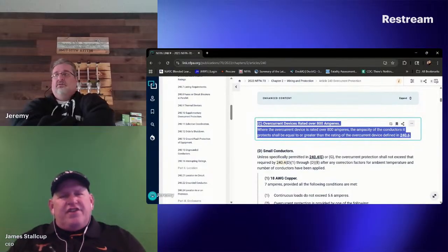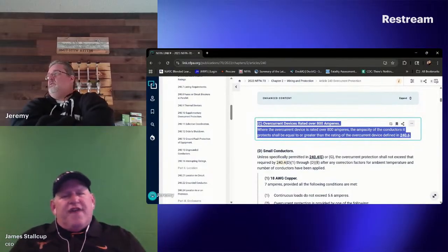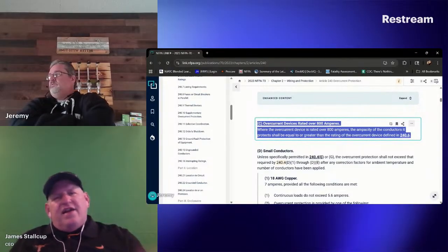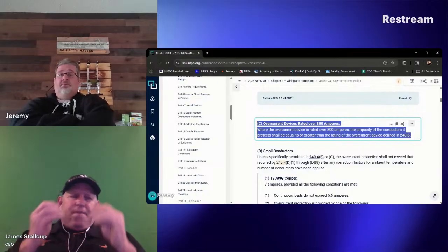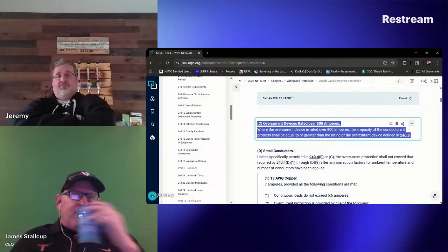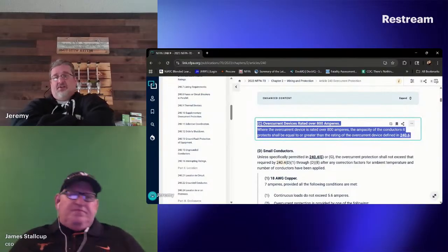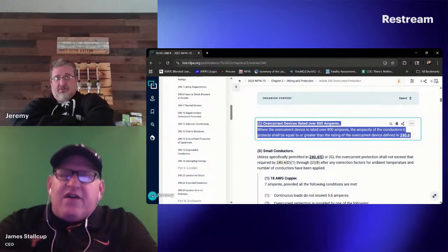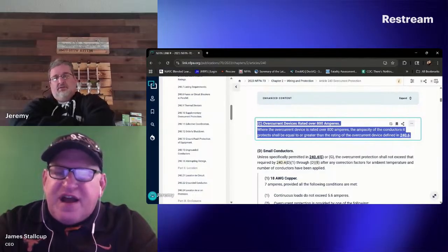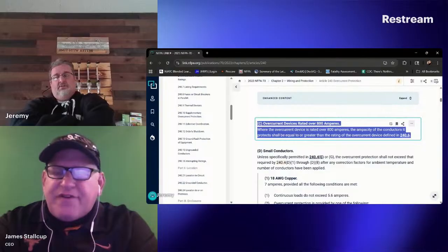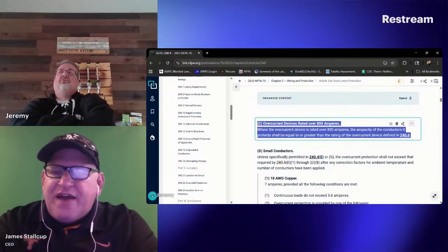You do your calculation. That's where your 125% is for continuous and 100% for non-continuous. Once you calculate that, 215.3 tells you to go where? Article 240.4(B), come over here and here's your rules. But it also says the OCPD has to serve 125% of the continuous load plus the non-continuous, which is 905 amps in our case. This is why you're allowed to go down to that 900 amp, because they realize that 125% is not going to be operating the whole time for everything on that service. So you've got diversity in there.